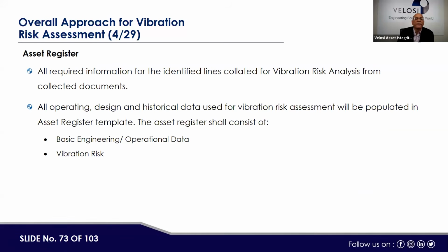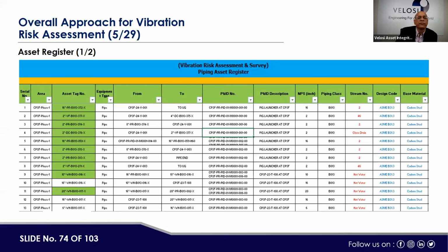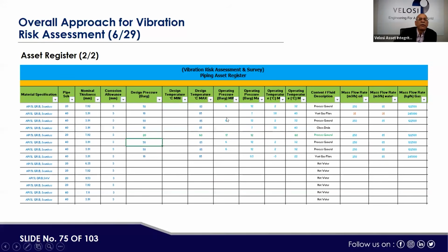Asset register, first of all, we prepared all required information for identified lines, collated for vibration risk analysis from the collected documents. All operating, design and historical data used for the vibration risk assessment was populated in asset register template, which included basic engineering and operational data and the vibration risk assessment as well. This is the piping asset register: the asset tag or piping tag number, equipment type, whether it's pipe or some other equipment, from-to P&ID number, P&ID description, diameter, piping class, stream number, design code, base material, piping schedule, nominal thickness, corrosion allowance, design pressure, design temperature, operating pressure, operating temperatures, and fluid mass flow rate, both for oil and water or gas.